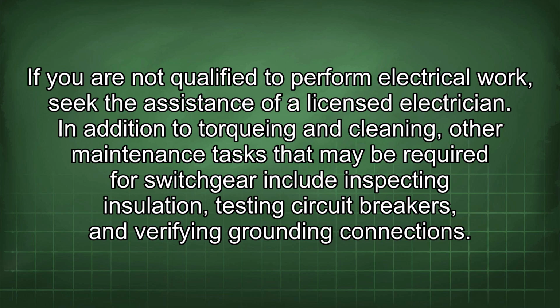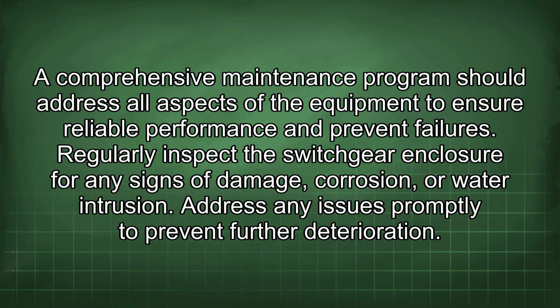In addition to torquing and cleaning, other maintenance tasks that may be required for switchgear include inspecting insulation, testing circuit breakers, and verifying grounding connections. A comprehensive maintenance program should address all aspects of the equipment to ensure reliable performance and prevent failures. Regularly inspect the switchgear enclosure for any signs of damage, corrosion, or water intrusion. Address any issues promptly to prevent further deterioration.